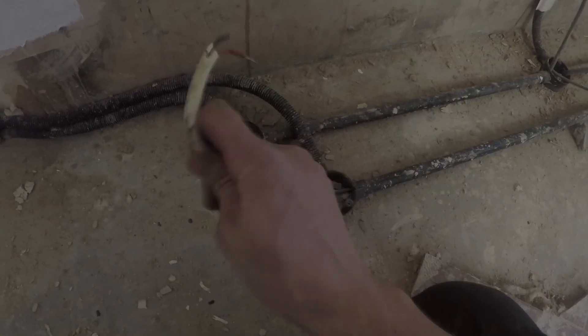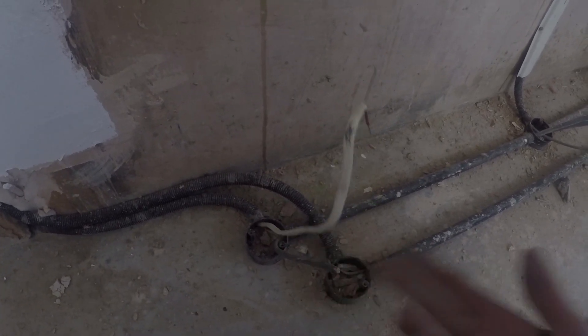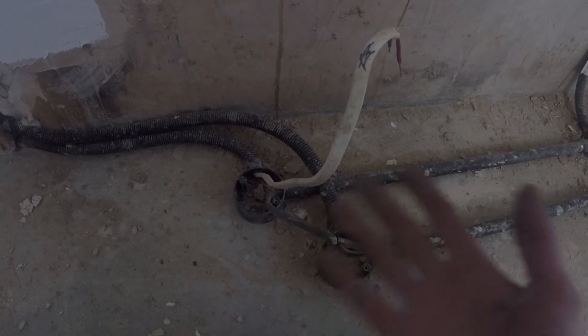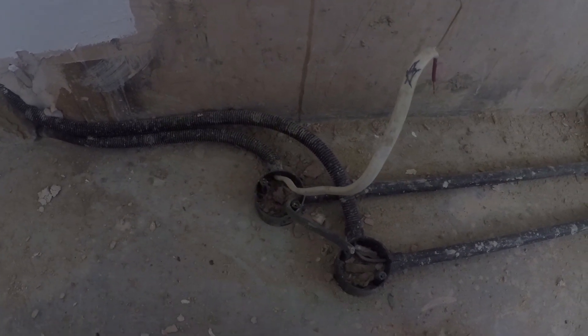This here was the old incoming leg from the kitchen. That was the reason I put this box here. This is just going to be on a 20 amp ring — I'm not going to bother putting it on a 32 because I'm always a believer: keep the fuse as low as you can get away with, without causing an inconvenience to the user. A 20 amp breaker in a kitchen will actually be more than ample. I'm just going to put some maintenance free connectors in there and put a waterproof gasket and a lid on it. What I will do though is in the back of the cupboard, I'll just cut a little hole with a blank plate on it, so if they do need to get to it for future testing or whatever, it is there if they need it — just as good practice, so to speak.